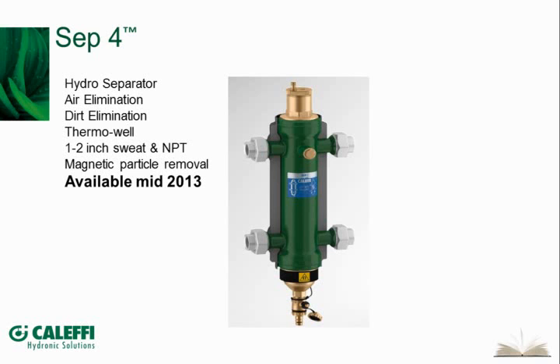And what else did we have? This is a new product, the SEP4, a true 4-in-1 device. What we did here is put the top of our regular air separators on it, so that's a serviceable top, you can get to the float and the stem on top, and we put the magnetic band on the bottom, so now you've got hydraulic separation. It's a 4-port hydro separator. We've got full-length media in there to do a good job of air removal at the top, dirt removal at the bottom, a convenience port for a sensor well or temperature gauge near the top, and we've added the magnetic band to the bottom.